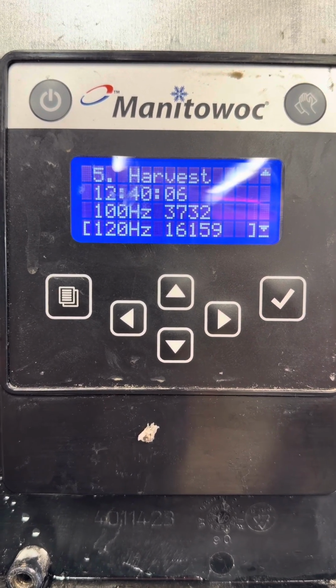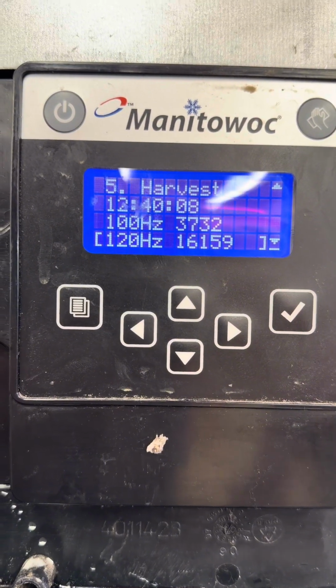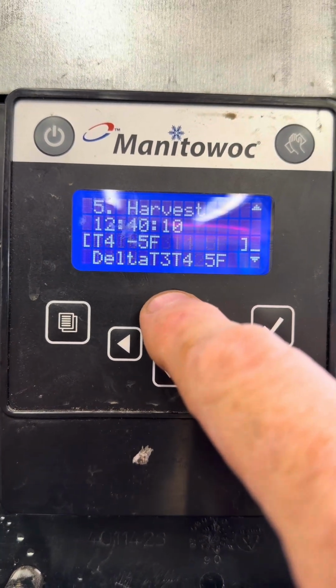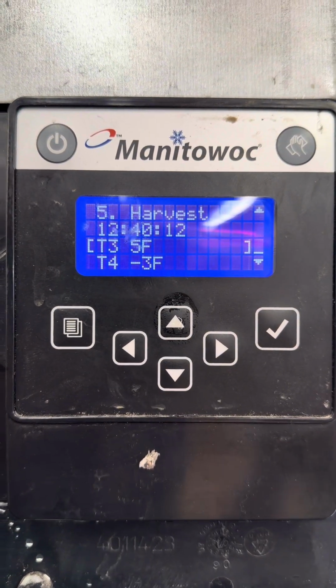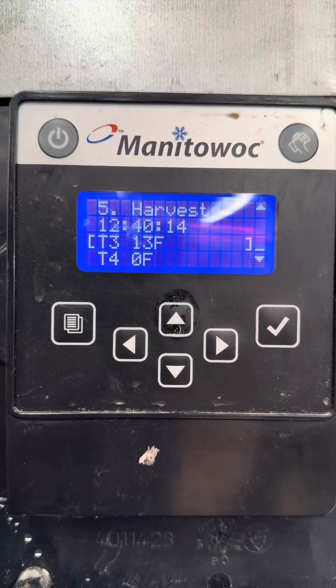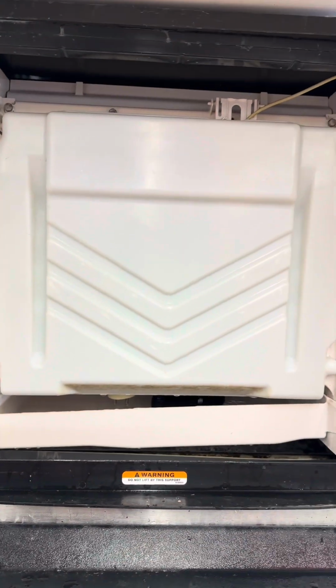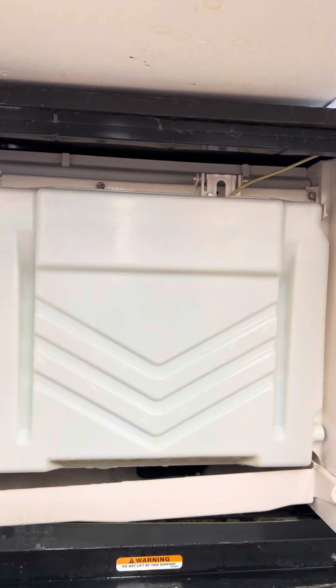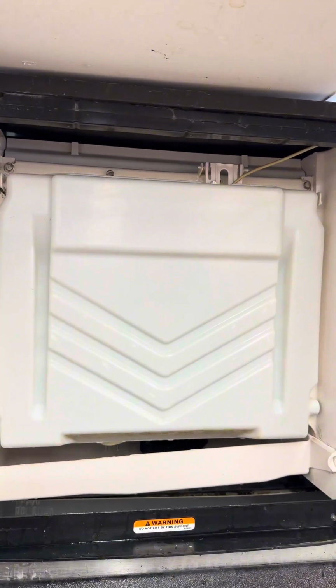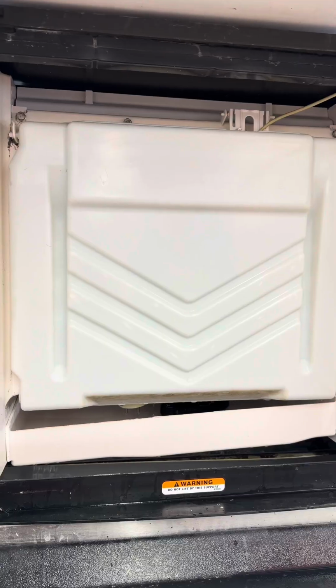So the machine is going to harvest mode now, and T3 and T4 start to warm up, and that coil will be hot enough to melt the ice, and the air pump is going to pump the ice out of the coil.